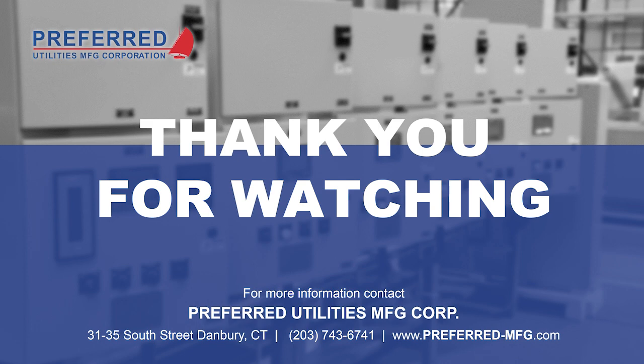Also a question here, can certain points along the firing rate range, or curve, if you will, be modified without having to adjust all the points? Yes. Most companies call that like adjust ratio. So you could actually step through the different points along the firing rate range and go in and make some adjustments, save just that particular point, and then you can exit commissioning without affecting anything else. And that's a real great advantage.